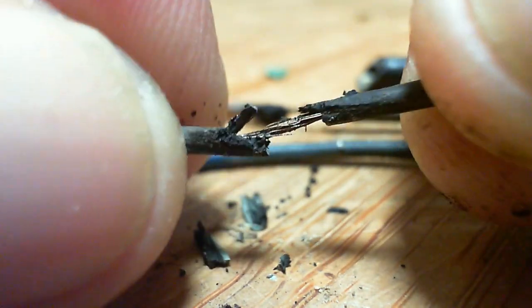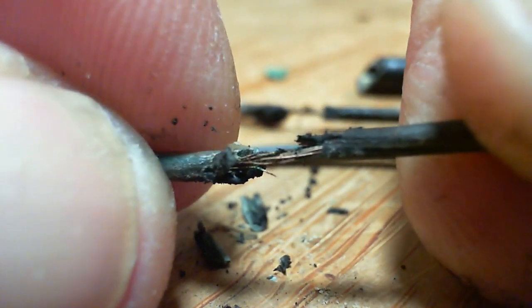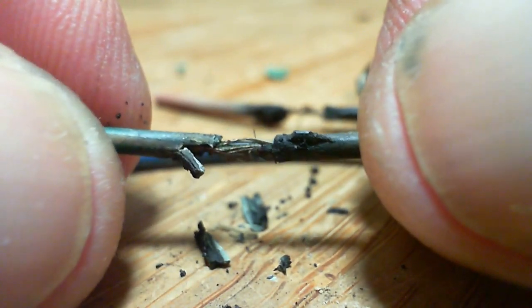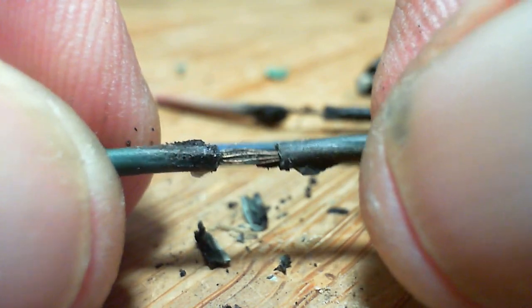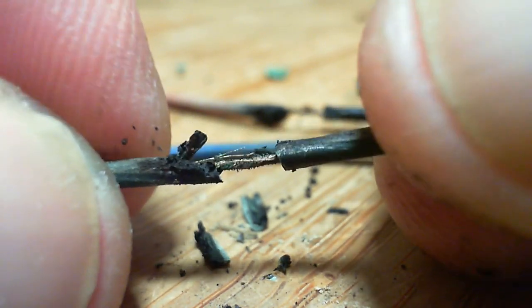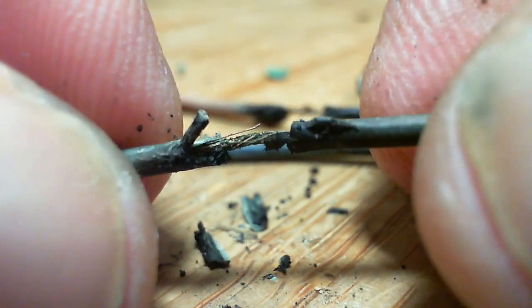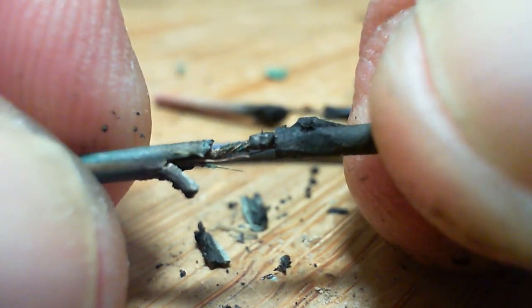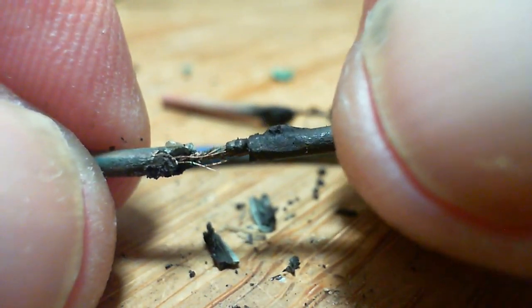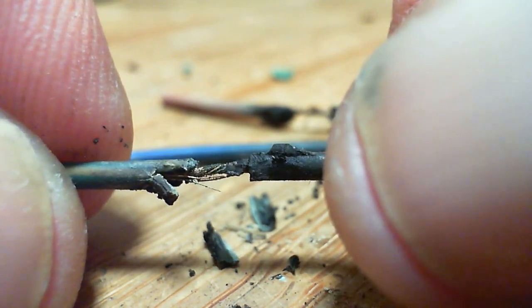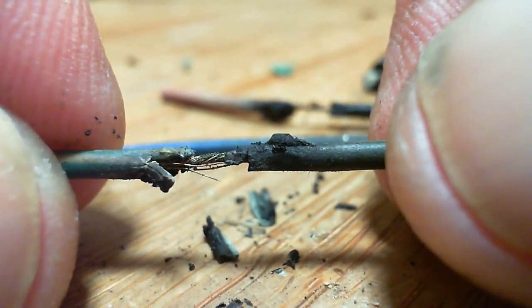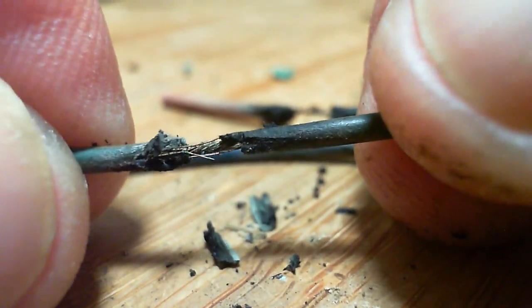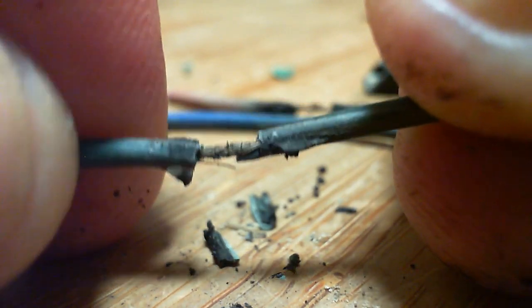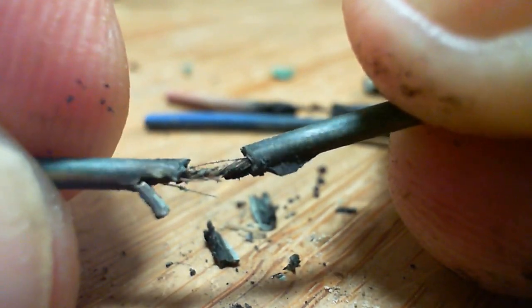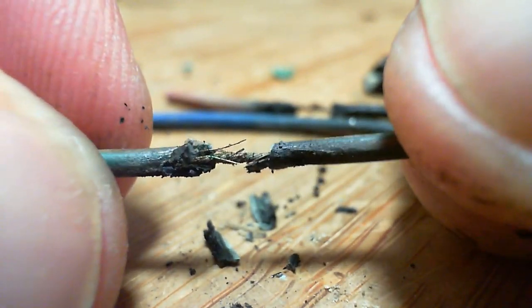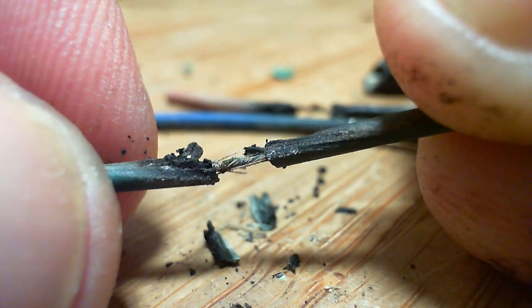So always one of the possibilities is a manufacturing defect. When they're making cables, they're making the strands, you see. They're bundling the strands into a cable, cabling them. Look at now, you can really see the broken ones. But, you know, they can't make a length of copper that's infinite. So at some point, even inside cables, there are splices made, right from the manufacturer. I don't see any evidence of that here whatsoever. Whether that would happen in this kind of wire, I doubt it.